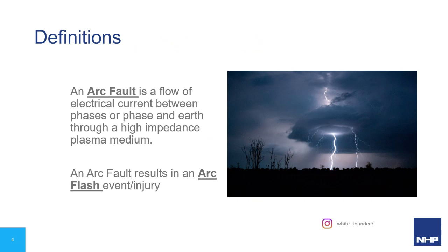A little bit here on the definition. An arc fault is the flow of electrical current between phase or phase to earth through a high impedance plasma medium. Usually that's through air. And an arc flash is the event or injury surrounding that. That's the definition between the two. You'll see them used interchangeably. They do mean effectively the same thing. But for me, arc fault is the actual electrical event and arc flash is the overall event.